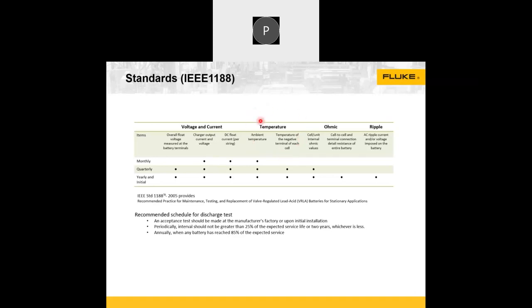Why is temperature important? Because the ambient temperature, and when the electrolysis process happens there is an increase in temperature. These two temperatures can actually deteriorate the electrolysis process as well as the electrolyte inside a battery. That's why temperature monitoring is important - especially in our system, the negative pole or negative probe is also equipped with a temperature sensor, so the temperature present at the negative pole you will be able to get.